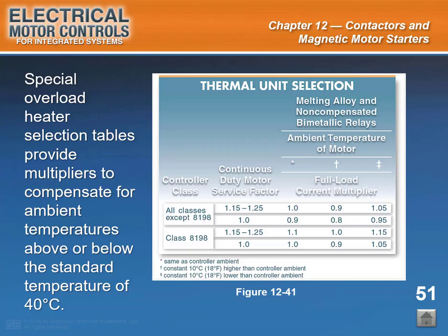Start of slide 51. Slide caption: special overload heater selection tables provide multipliers to compensate for ambient temperatures above or below the standard temperature of 40 degrees Celsius. See figure 12-41. As ambient temperature increases, less current is needed to trip overload devices. As ambient temperature decreases, more current is needed to trip overload devices.